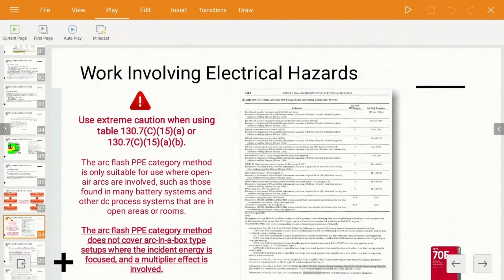And let me show you why. Here's what the table looks like. It's a close-up. In the table, it's got equipment in one column, and it tells you your arc flash PPE category, the level of PPE you should wear, and your arc flash boundary, that red dotted line. But if you look here, it says parameters for this 240 volts and below piece of equipment. It says you can't be exposed to any more than 25,000 amps of fault current, and the overcurrent protection device feeding that panel has to clear within 0.03 seconds or 2 cycles.